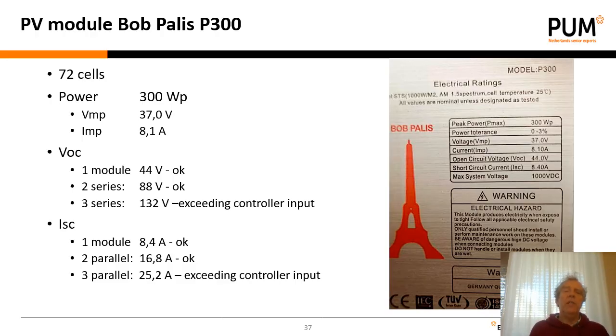So we're going to look at the PV module that we used in this example. It was a module with 72 cells, and we have here the specification of the cells. By the way, this is usually put on a sticker on the rear of each panel, so for most panels you can look that up very easily. If we look at the maximum voltage, one module will do at the highest 44 volts. So that means if we put two in series, we have maximum 88 volts. And remember that we could maximum have a voltage of 103 volts, so that's okay.